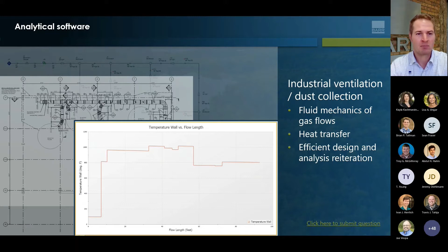We were able to do 3D design of the new ductwork and then import the geometric design into the analytical model to determine things such as correct ductwork materials and thicknesses, and insulation specifications and thicknesses, to optimize the new ductwork design to achieve the heat and friction goals of the new design system. This made for really efficient reiterations of the design to optimize the mechanical criteria.